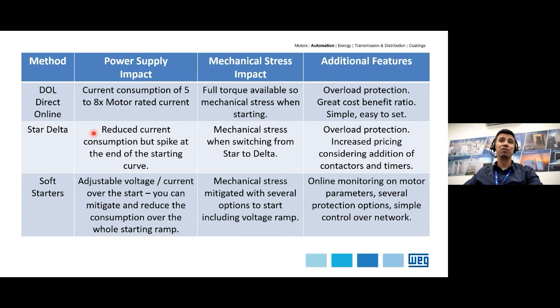On the DOL we have the full starting torque available, and its accelerating torque is very high, abrupt, aggressive, and that's usually not good from the mechanical point of view because it brings stress, fatigue, wear, potentially vibration and failures. But if you have an application where you're not starting too many times an hour, or if you're starting one time a year, for example, maybe that's something you can deal with.